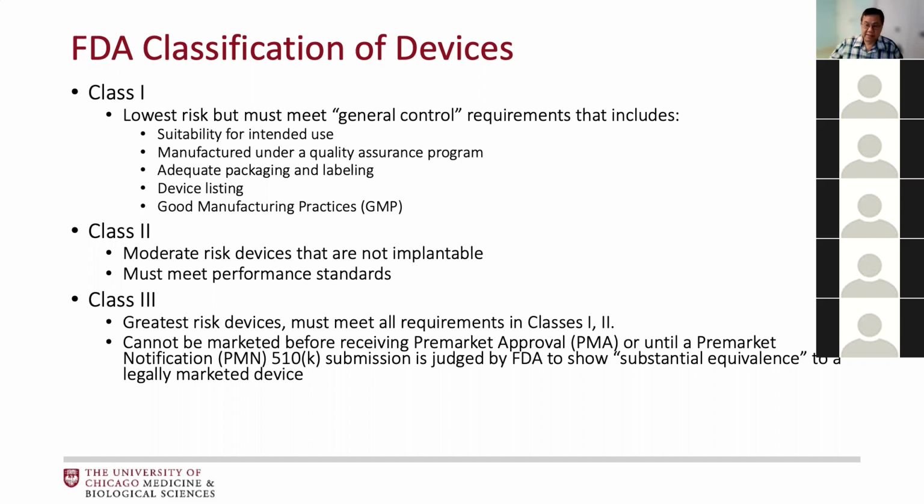There's another whole category that I have not talked about yet, called lab developed tests, and I'll talk about that. But any test that's approved for a particular indication in molecular is usually a class 3 device, right? If something has to be implanted into the body to get a constant reading, that's typically also a class 3 device. Most of our tests are not implantable, but we are moving towards an era where we might be seeing some of those implantable devices, if not already there. Okay, good.